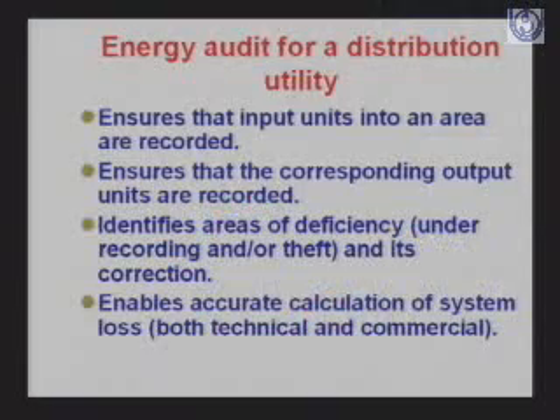Let's come to your system, that is the distribution utility. Energy audit would help ensure that input units into an area are recorded - that is, from the substation, when energy is dispatched, we will have a clear indication of how much energy we have sent. It also ensures that the corresponding output units are recorded from the distribution transformers.